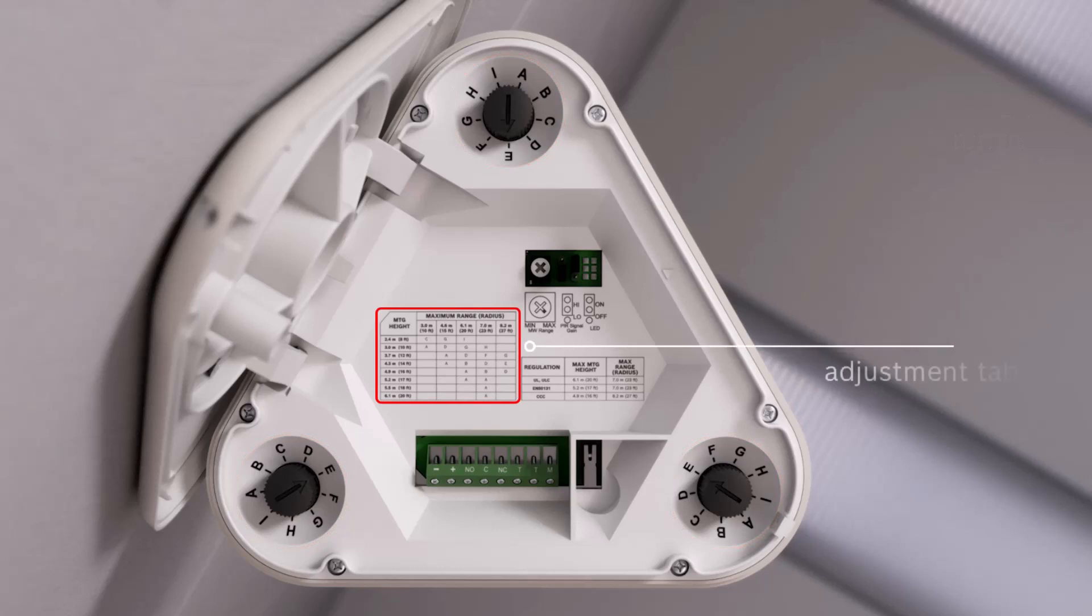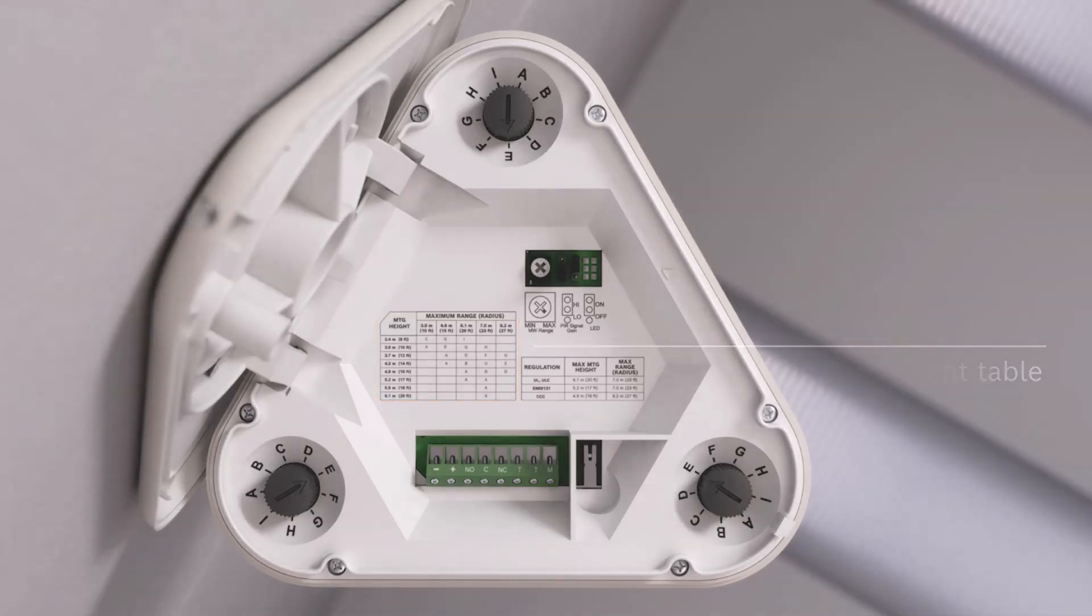Coverage pattern is determined by both mounting height and the size of the radius. Not every setting can be used for each mounting height. Use this table to tell you which settings are available for your mounting height.